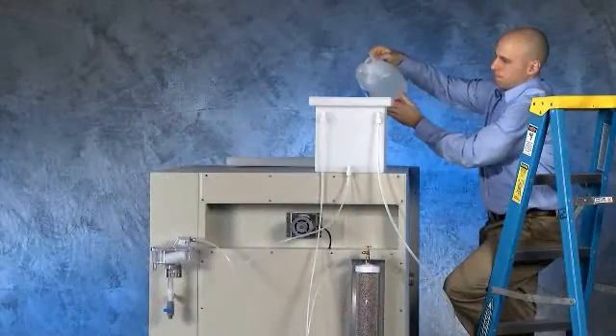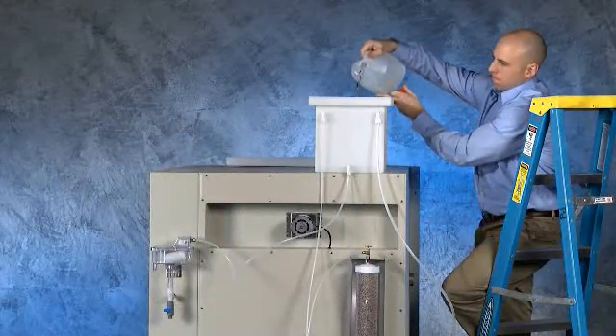The water storage tank is filled with six gallons of single distilled water. The water flows from the reservoir directly into the steam generator. The steam condenses in the chamber and is drained into the water recirculation pump. The pump then forces water back through the demineralizer system where it is cleaned to remove test contaminants. The filtered water is returned back into the water reservoir to be reused in the steam generation process. The water recycling system is a closed circuit and requires no plumbing or drainage setup.